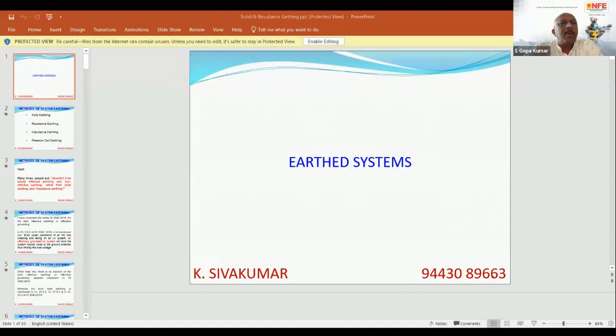This is related to resistance earthing in mines, where the current has to be limited to less than 750 milliampere, and how the protection, the disconnection, is achieved, is the question. You have to have an earth leakage relay, sir. I will just have to refer. There is a definite section in NEC for mines, no? Yes, and there is for CE also, mines protection is there. Generally, if you have a 750 milliampere earth leakage current, you always go for an earth leakage relay which has a 750 milliampere setting, and that relay's output contact you connect to your VCB, possible.